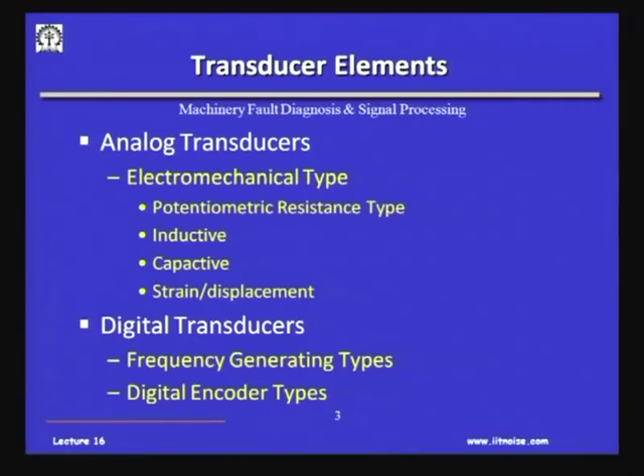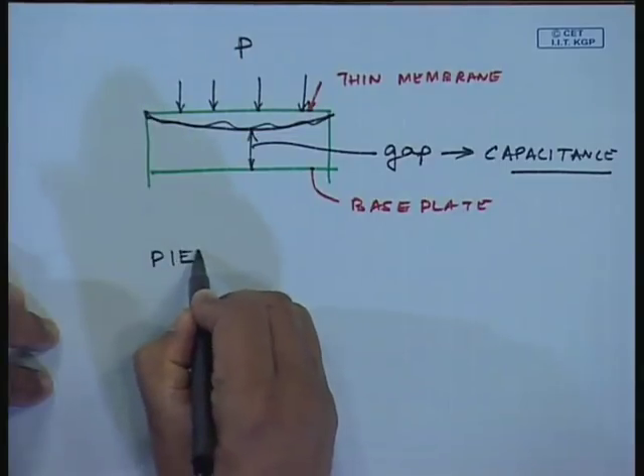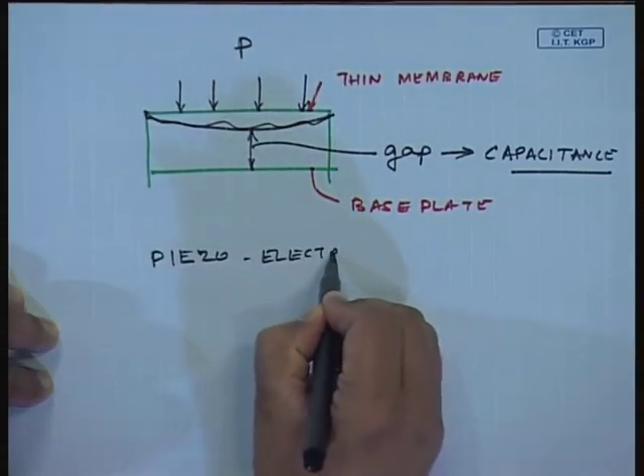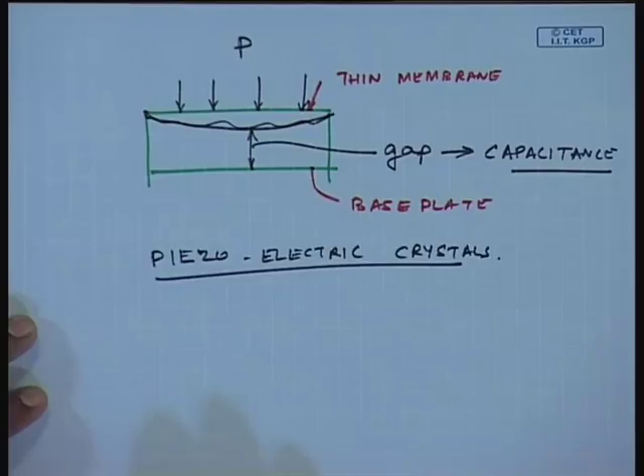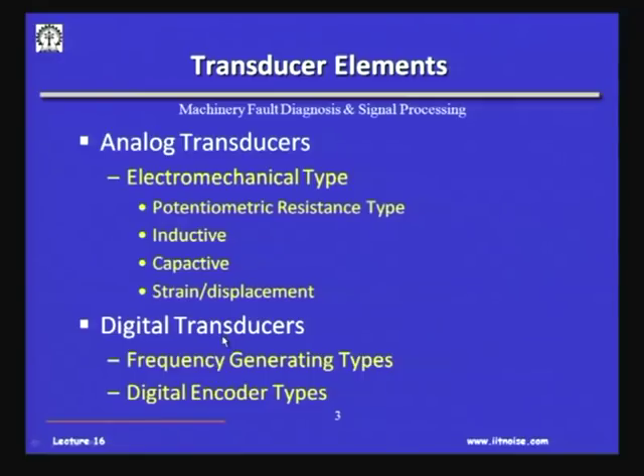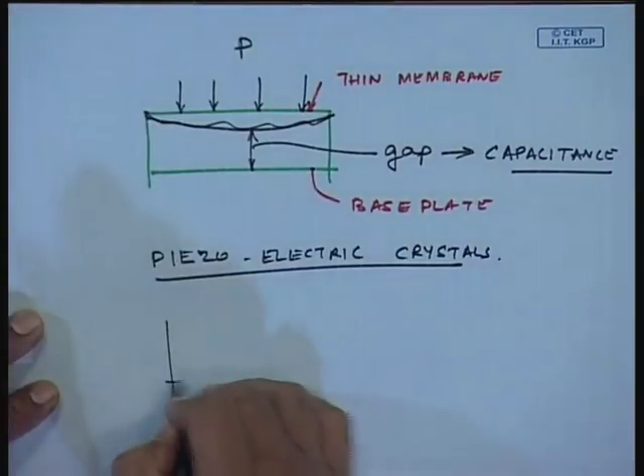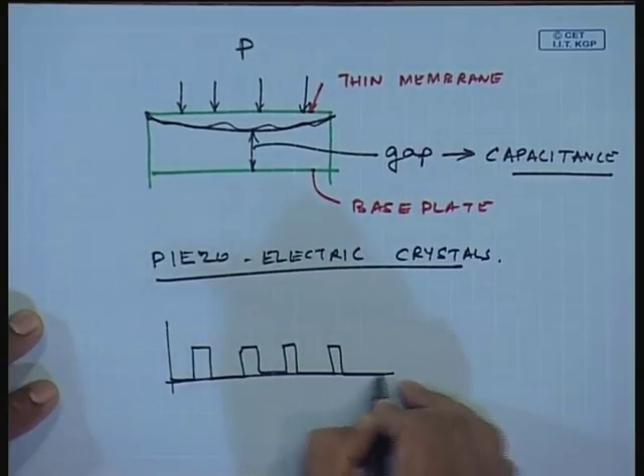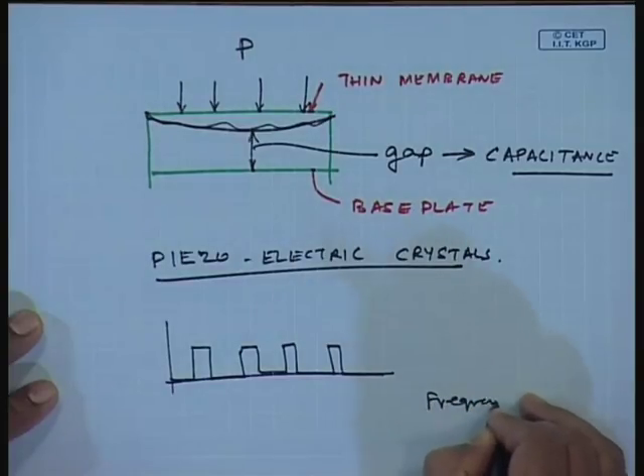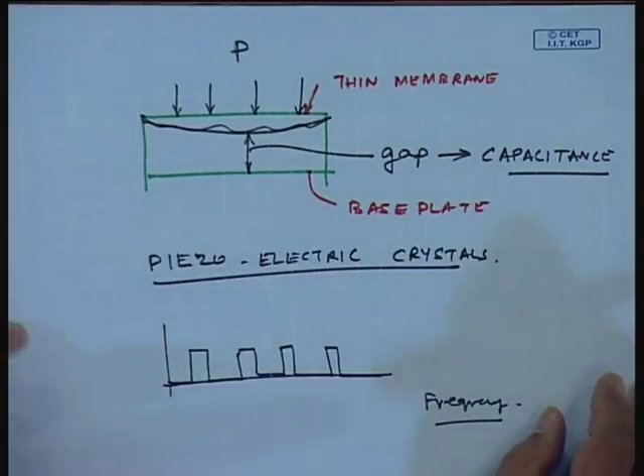Instead of strain gauges, piezoelectric crystals are also used nowadays. In CBM, some instruments use piezoelectric crystals as the sensing element. Digital transducers generate frequency-based or digital encoder-type outputs, generating a pulse train. By measuring the pulse width, we get the frequency estimation, and these are used in CNC machines, lathes, etcetera, to find out speed fluctuations.